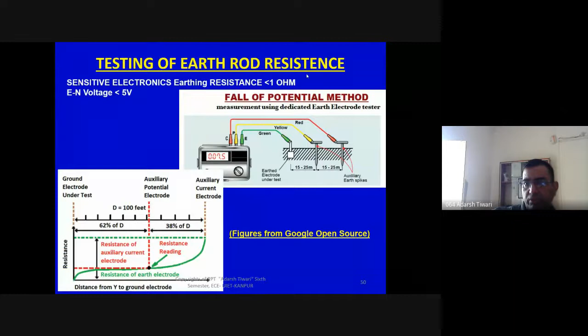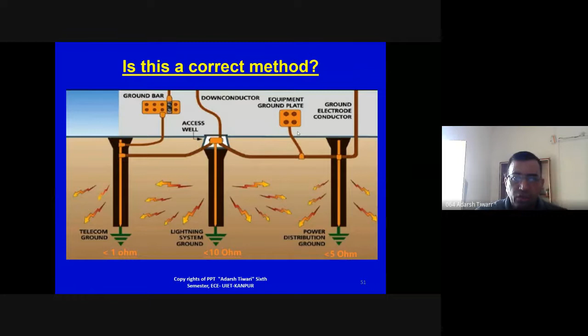But if you see some electronics installations, what is done? All the telecom equipment requires less than 1 ohm, the lightning arrestor requirement is 10 ohm, and the power system requirement is 5 ohm. They are connected like this. This is a wrong practice. Whenever we have to ground different equipment in the same building, the grounding of different equipment should be separate. You may do parallel grounding of telecom, and you may form a grid of telecom grounding together, but this is not a good practice. This is very common to save on grounding. People do this, which is not an accurate method of grounding.